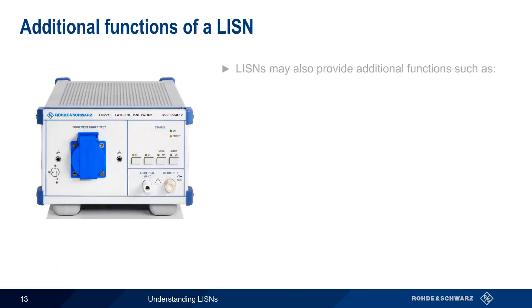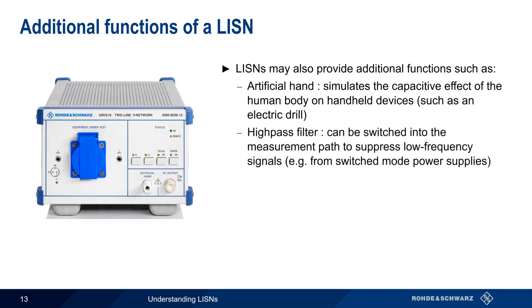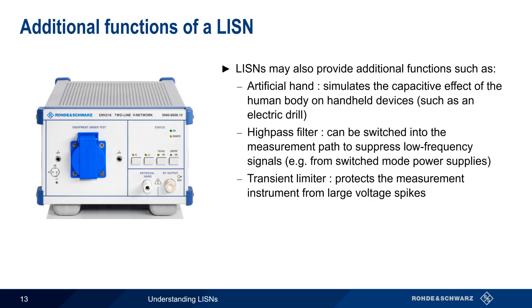As mentioned, a LISN may provide additional functions. One of these is an attachment for an artificial hand, which simulates the capacitive effect of the human body on a handheld device — for example, an electric drill. A switchable high-pass filter can be used to suppress certain types of low-frequency signals, like those from switched-mode power supplies. Transient limiters may be provided as a means of protecting the measurement instrument from large voltage spikes. And finally, remote control allows a LISN to be controlled by an attached measurement instrument or by an automation environment.